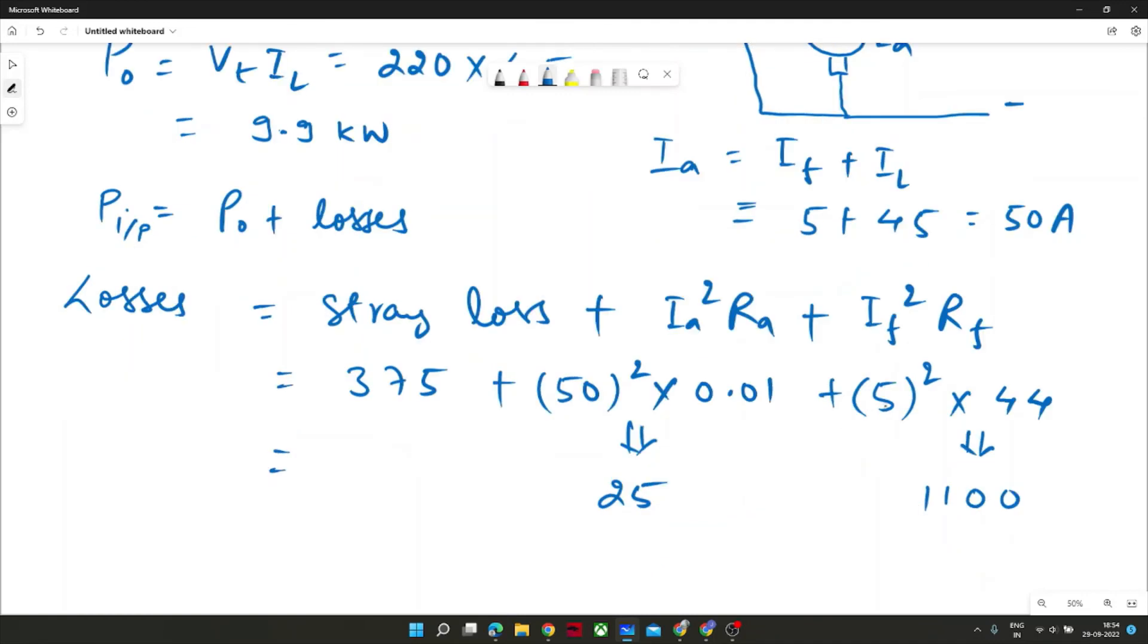So you can see significant loss, copper loss is happening in field component. And in armature resistance, since it was very small, so negligible amount. So total losses, if I add, it can be 1500, 1500 watt in total losses.